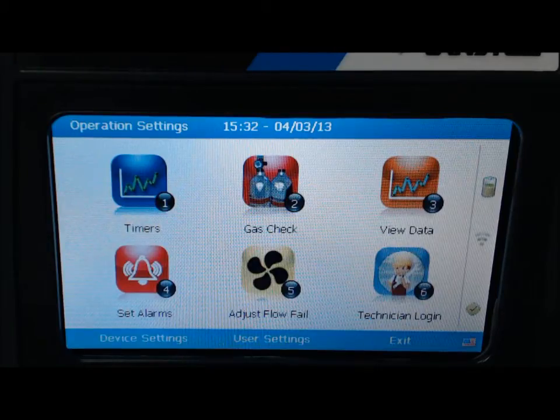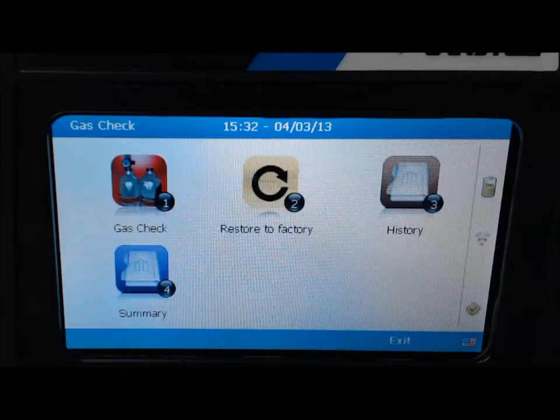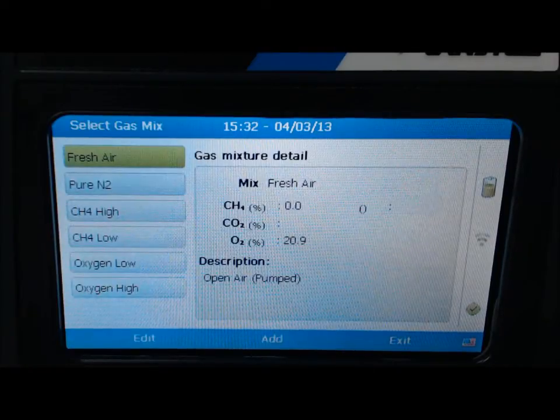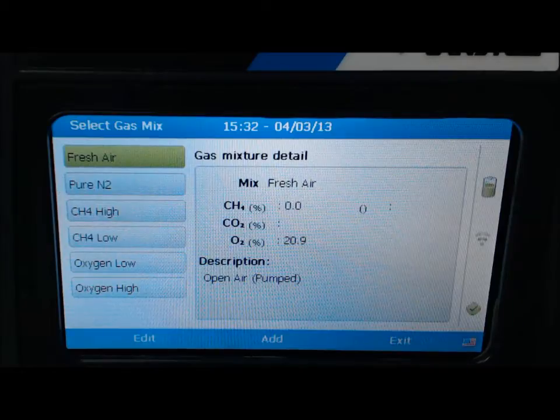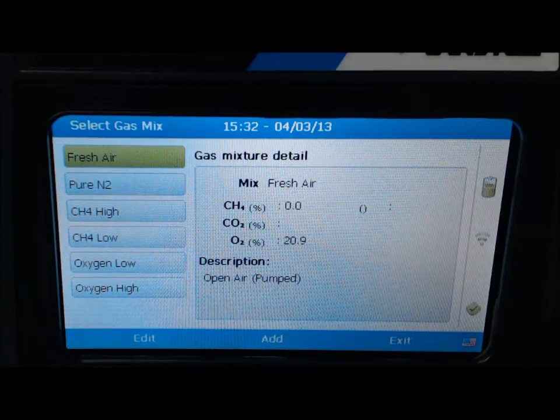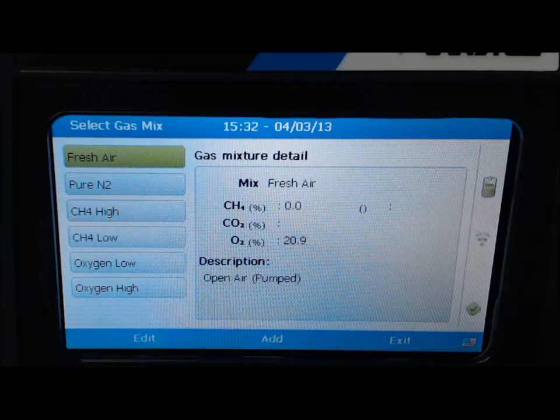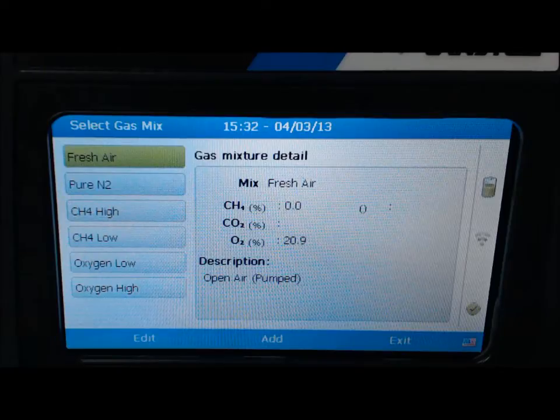Select 2 for gas check, then select 1 to continue. From the select gas mix screen, you will notice as a default a list of 6 gas mixtures, each gas mix with its predetermined gas concentrations. From the list of gas mixes, you need to select a gas mix to zero and a gas mix to span and/or calibrate your instrument.